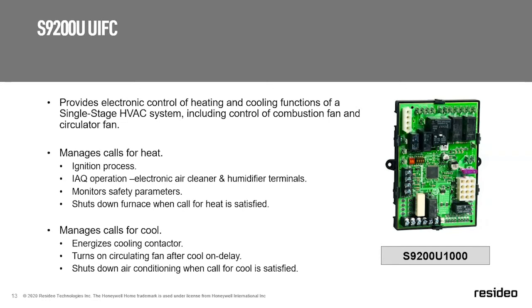It does monitor safety parameters, so your different limit switches and things. There are safeties built into here, and it shuts down your furnace when your call for heat is satisfied. So it'll manage your calls for heating. What it also does is manage your calls for cooling. It will energize your cooling contactor based on a call for Y, which is your cooling signal, and it also turns on your circulating fan after your cool on delay. There are dip switches that you can use to select what your fan off delays will be.